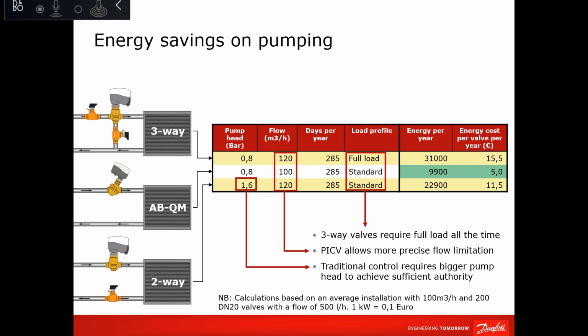And why is that? As we said, if we try to modulate a two-way valve, which has a poor authority, let's say 0.4, then we will be able to modulate from 100% to 60%. While with PICV, which can go to 10% opening or less, the difference between 60% and 10% is 50%. And that's what explains in this table that the cost of the PICV on energy per year is half the cost of a two-way valve. And this is the effect on the running cost.